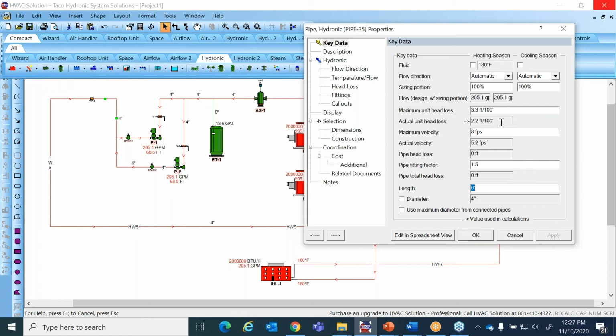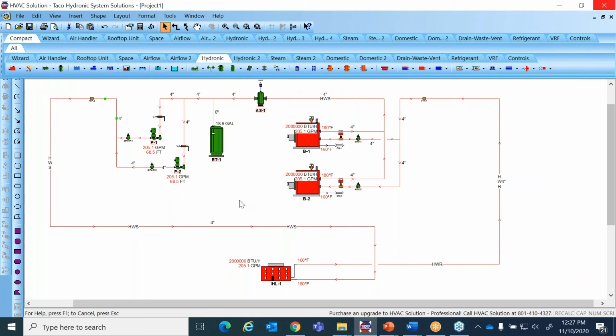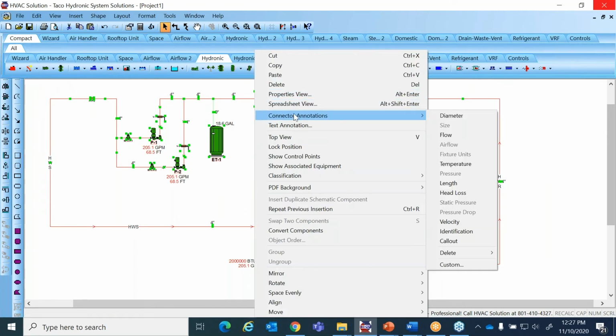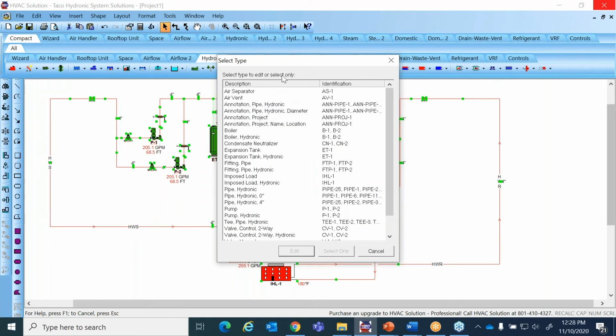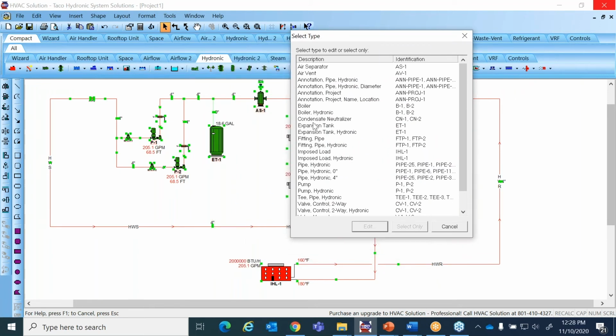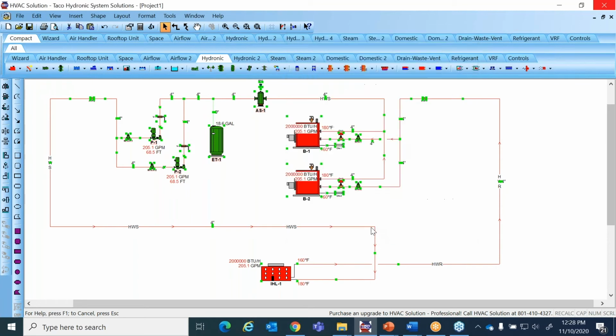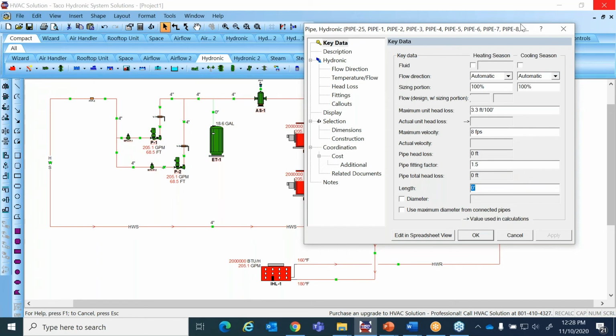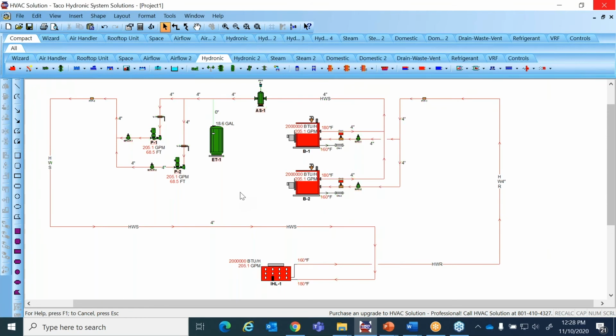To me they're pretty standard numbers, maybe that unit head loss is a little low, but you can change that. Let me show you what I mean - I want to change the maximum unit head loss for all the piping. If I hit Control A and right click, this time instead of Connector Annotations I go to Property View to globally change the pipe. Clicking on pipe and hitting Edit gives me access to all of the pipe, and I can change that to 4 feet per 100 instead of 3.3 feet per 100. It didn't affect my calcs, but I wanted to show how easy a quick global change is.